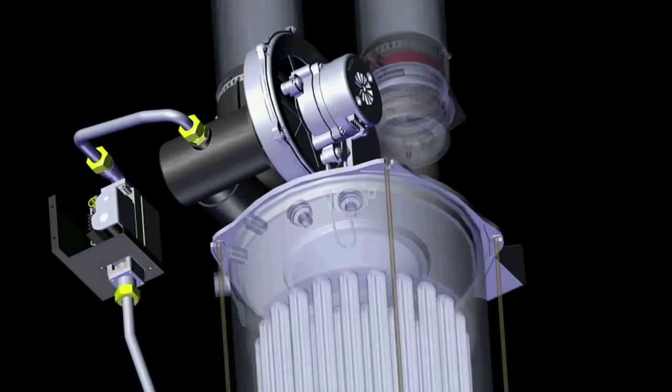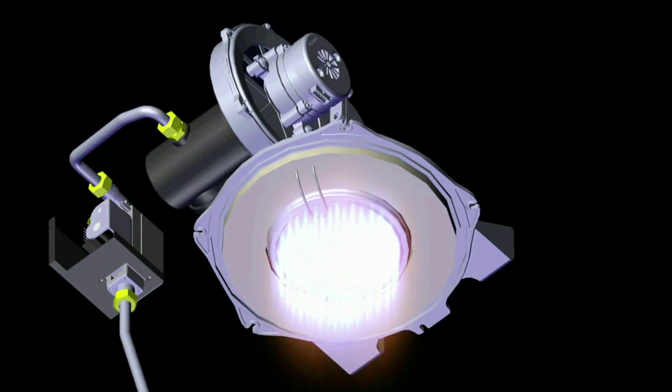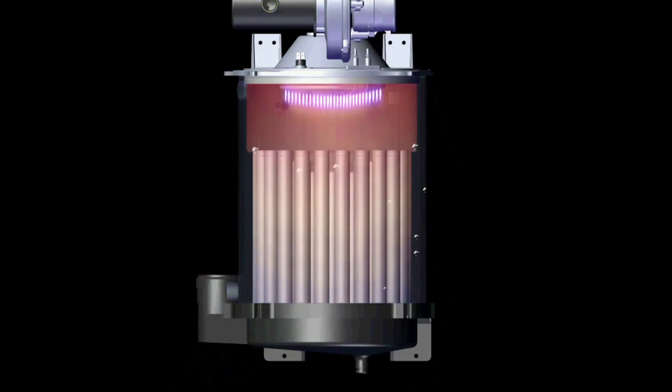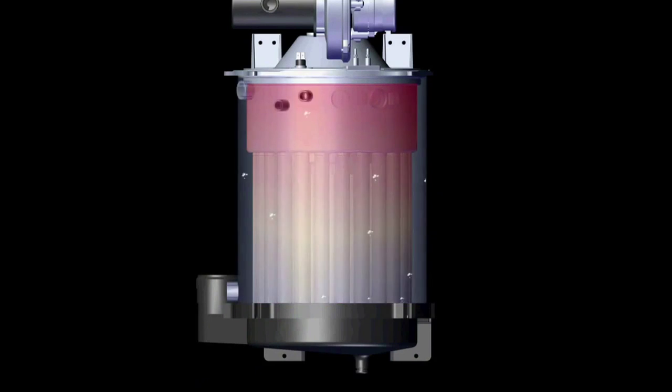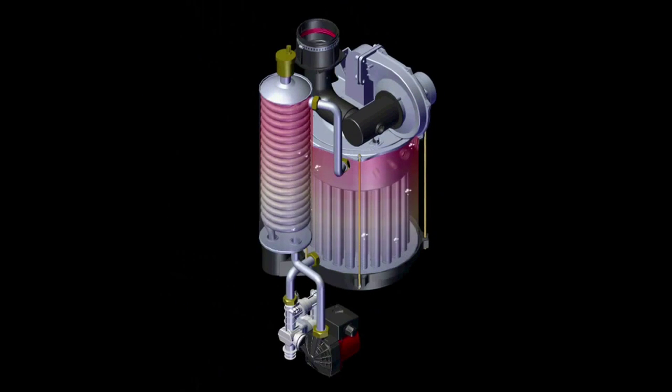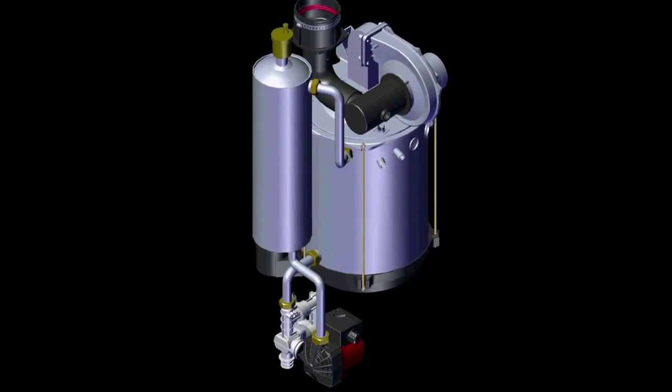At this time, the entered mixed gas and air are ignited with the spark ignition system. If the flame is sensed and the flame is not extinguished after 2 seconds, the boiler operates normally. Heat is exchanged rapidly through the highly efficient heat exchanger, transferring energy quickly to heat the system returned water. The internal central heating circulation pump will operate and circulate the heated water through the boiler heat exchanger and internal storage tank.